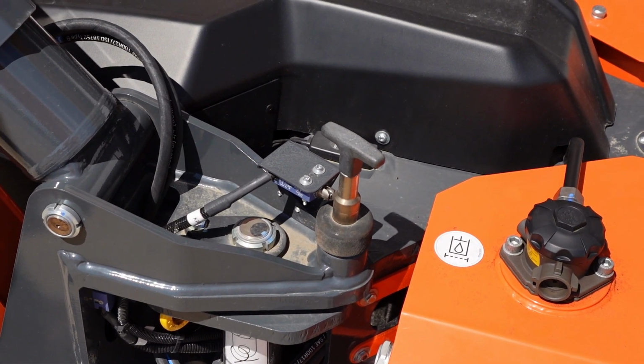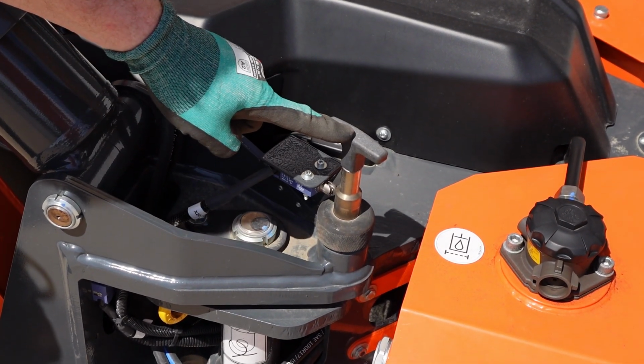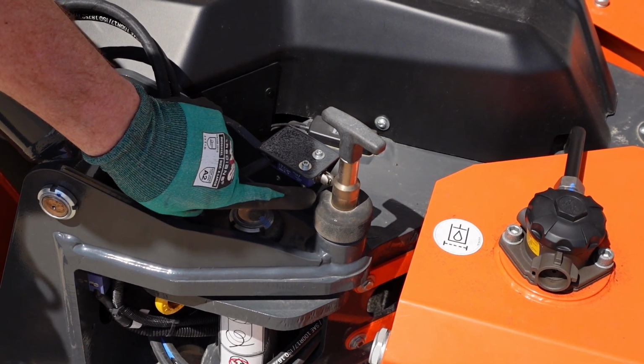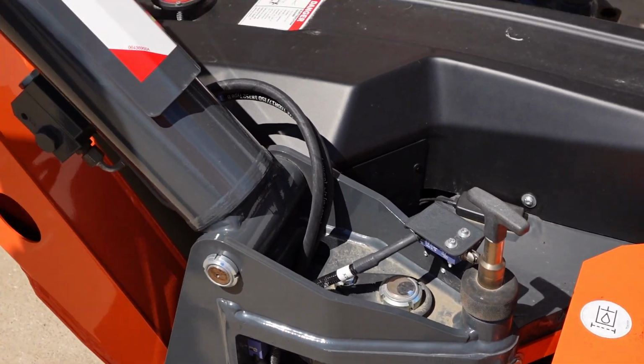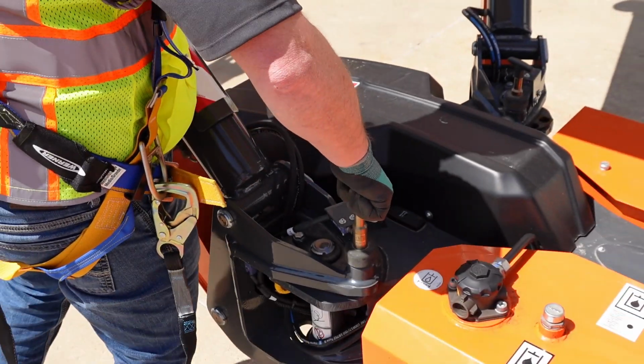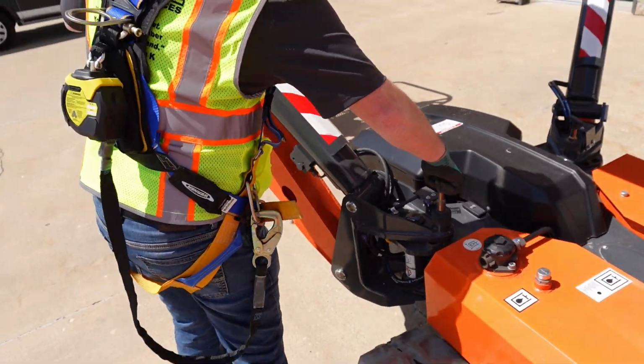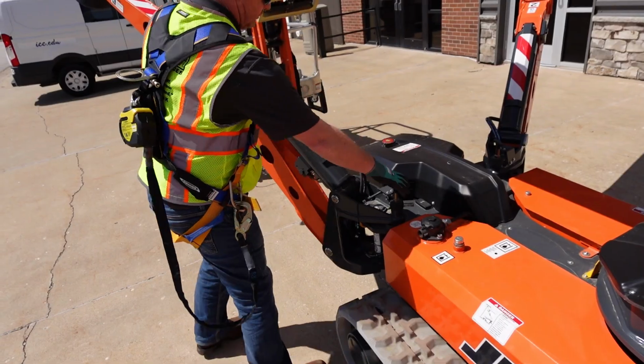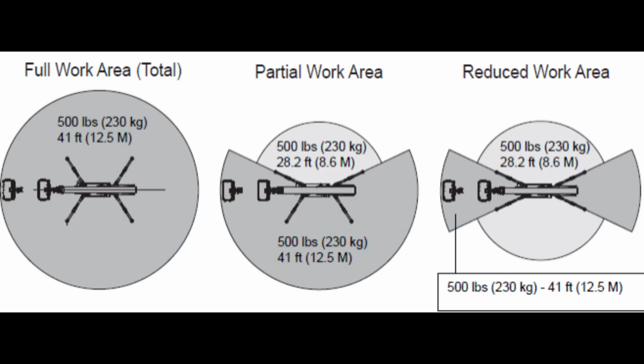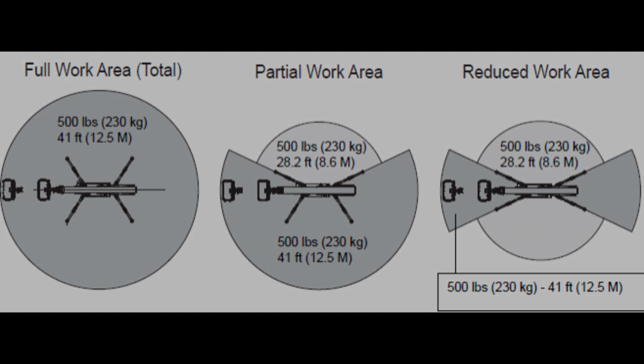The outriggers are held in place by manual pins. Each pin has a limit switch that reads the position of the pin and tells the machine if the outrigger is stowed, restricted, or open. When all 4 outriggers are in the open position, the machine is given its full working area. If 2 of the outriggers are moved into a restricted position, the machine will only be allowed a partial working area. If all 4 outriggers are in their restricted positions, the machine will operate in a significantly reduced area.